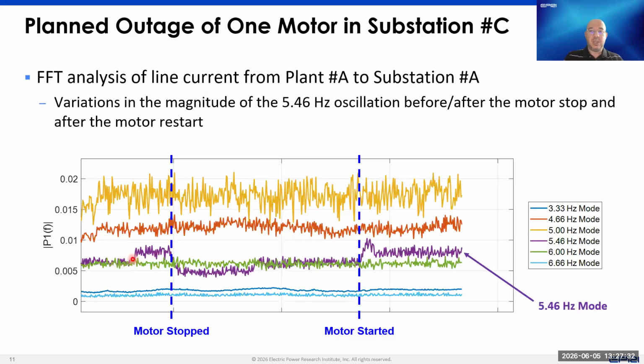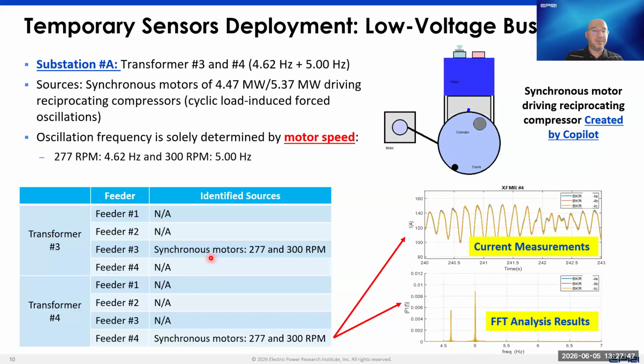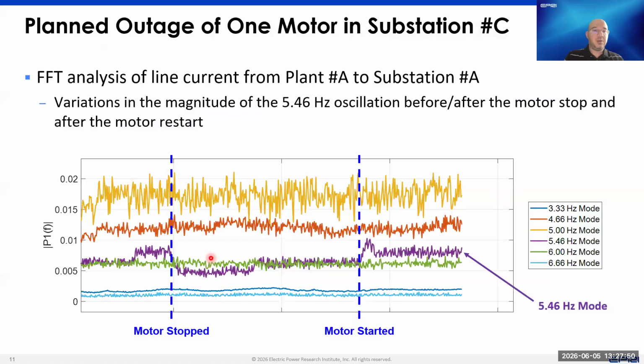I want you to focus on the purple line, which is the 5.46 hertz oscillation mode. What you can see here is that there are variations in the magnitude of the oscillation before and after the motor stopped, and also after the motor restarted. So what we suspect happened during that time period is that initially, before the motor stopped, the energy level of that oscillation mode is at a specific value.